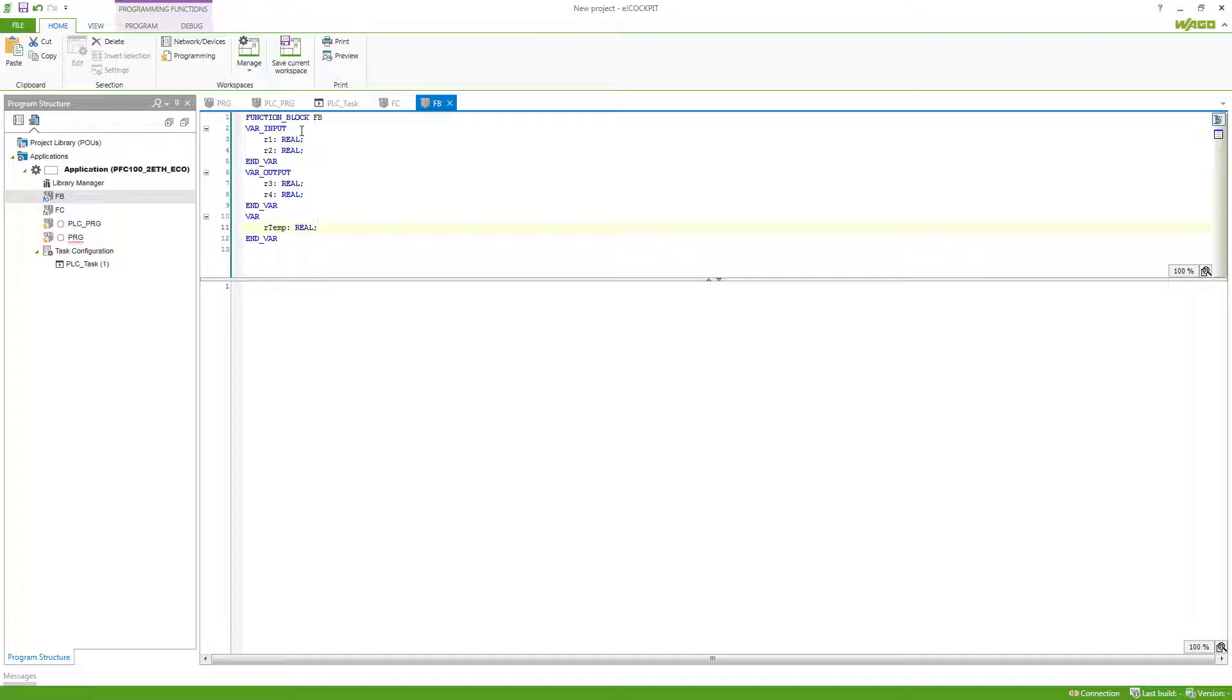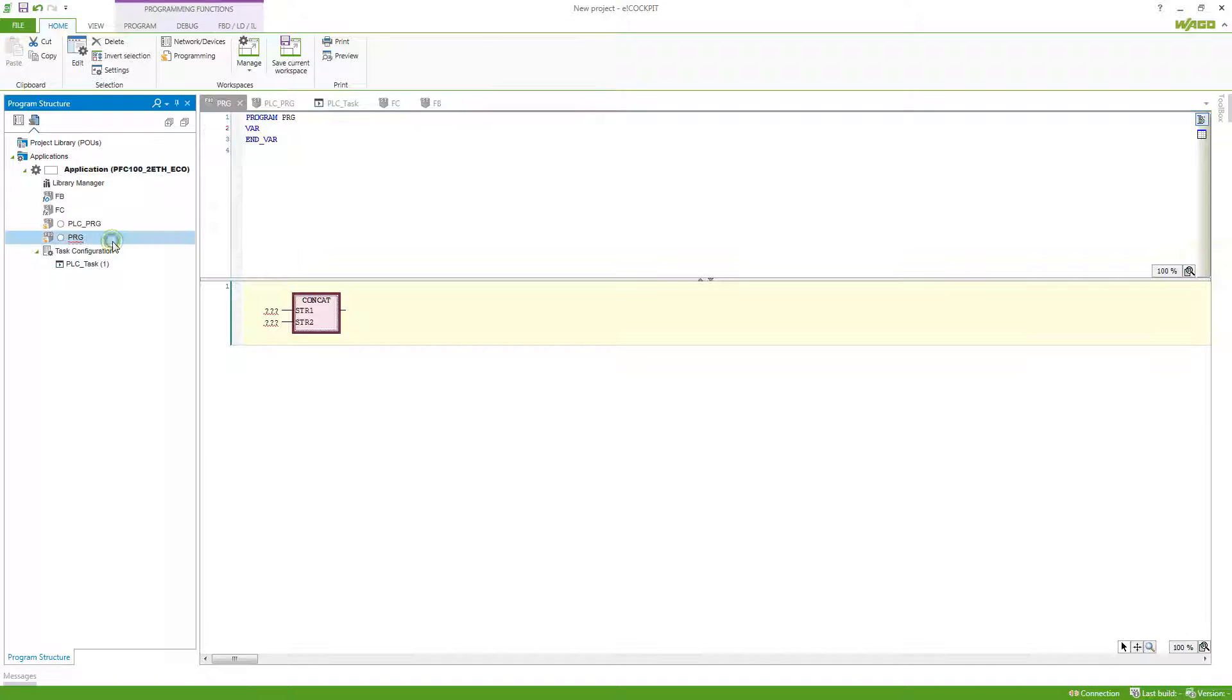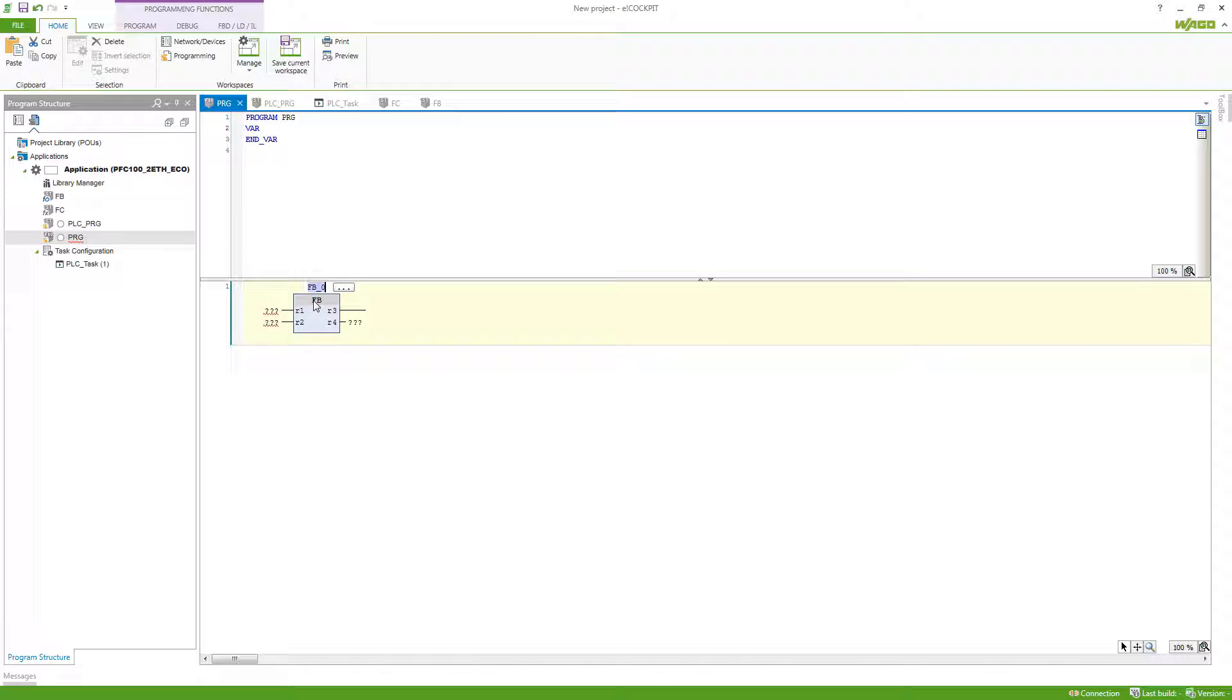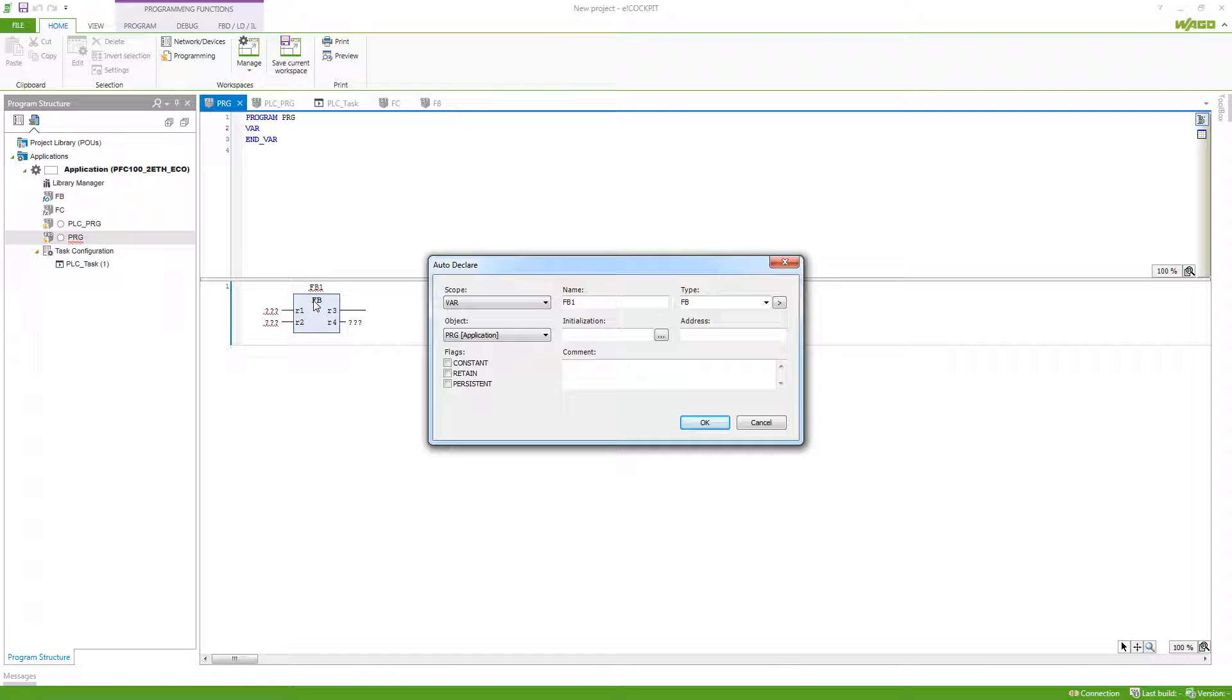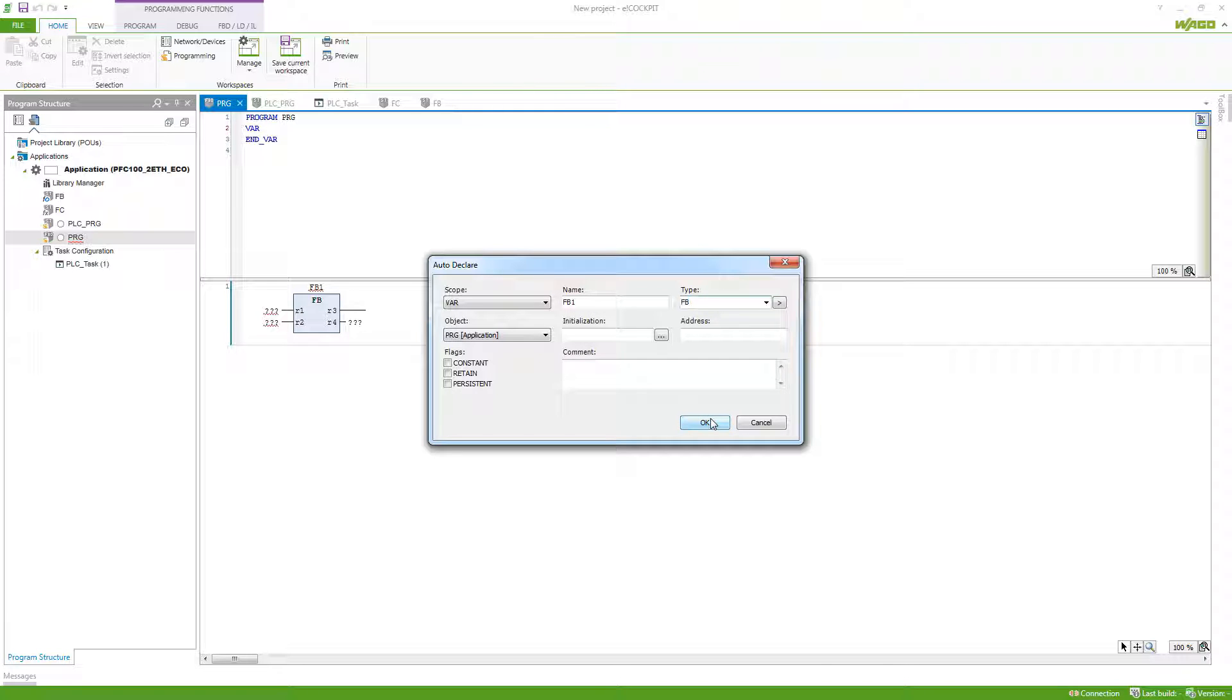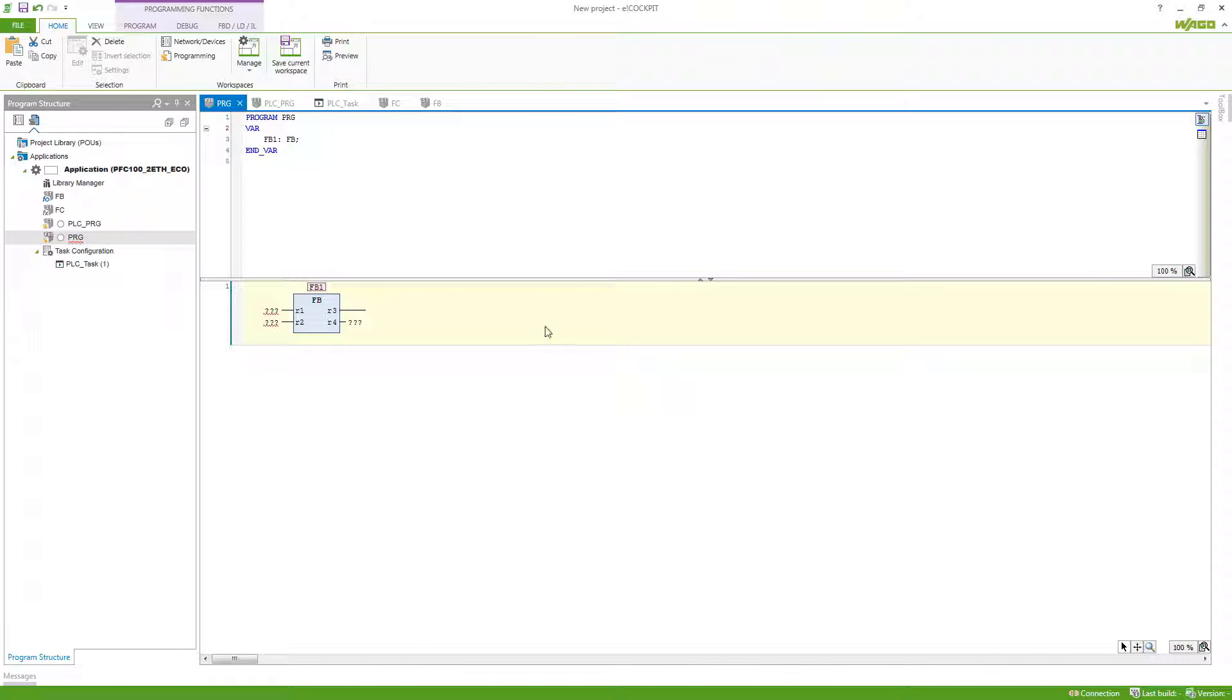In order to do this, a function block always has to have an instance. So if we go back to our program here and select now our function block, you can see that it requests a name. In this case, we'll just name it FB1, which then brings up the auto declare. So FB1 of the type FB, and if we hit okay, we can see that this function block is now part of the variables of our program, and so it is also located in the memory of the controller.